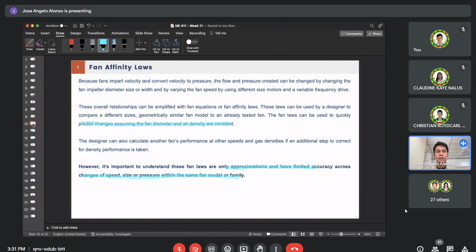Okay, so let's continue. Determine the new speed of the fan by increasing the power from 3.75 HP to 5 horsepower. So based on our fan affinity law, let's go back to our fan affinity law. Meaning, we will take this from variable speed and constant diameter, since our only option is to change the speed of the fan and maintain the diameter of our fan. So this is what we will use to determine, or to predict, the new fan capacity and new fan rotational speed.